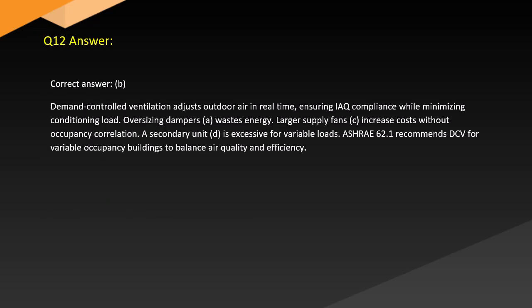Answer. Correct answer: B. Demand-controlled ventilation adjusts outdoor air in real time, ensuring IAQ compliance while minimizing conditioning load. Oversizing dampers, A, wastes energy. Larger supply fans, C, increase costs without occupancy correlation. A secondary unit, D, is excessive for variable loads. ASHRAE 62.1 recommends DCV for variable occupancy buildings to balance air quality and efficiency.